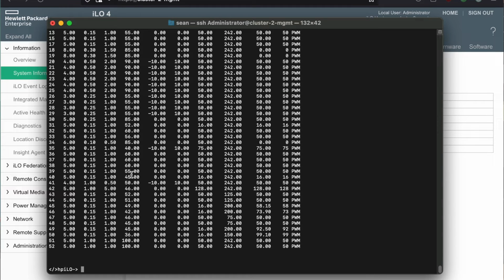now that we've done all that, the first one we did was 31. We can see 31 has a current speed of 16, so that's dropped way, way, way down. Then we did 40, which is also currently running at 16. That one worked. Then we did 45, which is currently running at 58. So you can see that depending on the sensor and what it's monitoring, it doesn't necessarily drop right down to the low. Sometimes it does sit somewhere in between. In this case, 58. In the case of 46, it's on 73. And in the case of 49 and 50, I'll run the command again. So you can see these ones are actually still up a little bit. I can tell you from experience, having done this before, these particular sensors will never actually drop to 16.